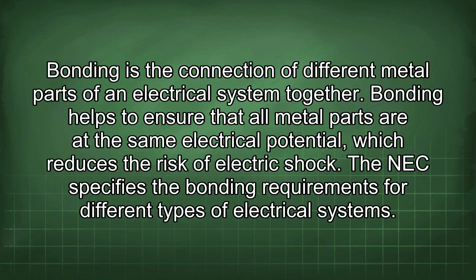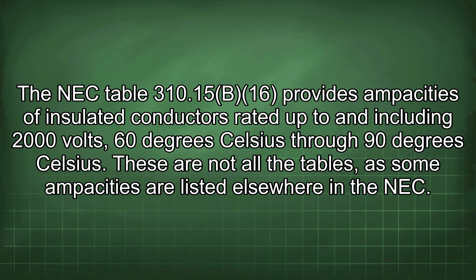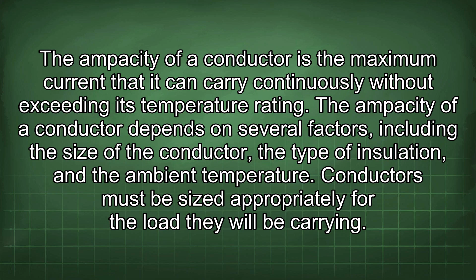NEC Table 310.15(B)(16) provides ampacities of insulated conductors rated up to and including 2000 volts, 60 degrees Celsius through 90 degrees Celsius. These are not all the tables, as some ampacities are listed elsewhere in the NEC. The ampacity of a conductor is the maximum current it can carry continuously without exceeding its temperature rating, depending on factors including the size of the conductor, the type of insulation, and the ambient temperature. Conductors must be sized appropriately for the load they will be carrying. If a conductor is too small, it will overheat and could cause a fire.